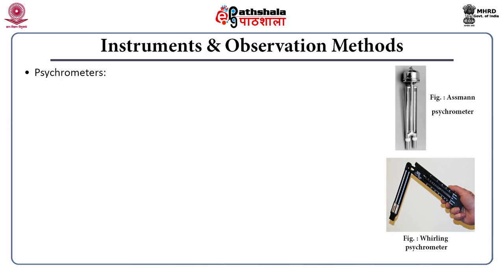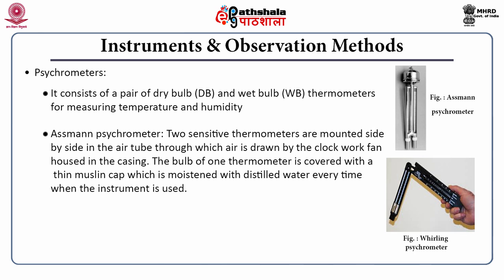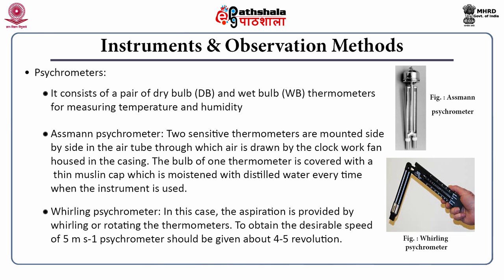Next is the psychrometer, which generally consists of a pair of dry bulb and wet bulb thermometers used for measuring temperature and humidity. There are two main types: the Assmann psychrometer and the whirling type psychrometer. In the Assmann psychrometer, air is drawn past the dry and wet bulbs by a clockwork fan. The bulb of one thermometer is covered with a thin muslin cap, which should be wetted with distilled water each time the psychrometer is used. In the whirling psychrometer, aspiration is provided by whirling or rotating the thermometers. The desired speed is 5 meters per second, obtained by giving 4 to 5 revolutions.